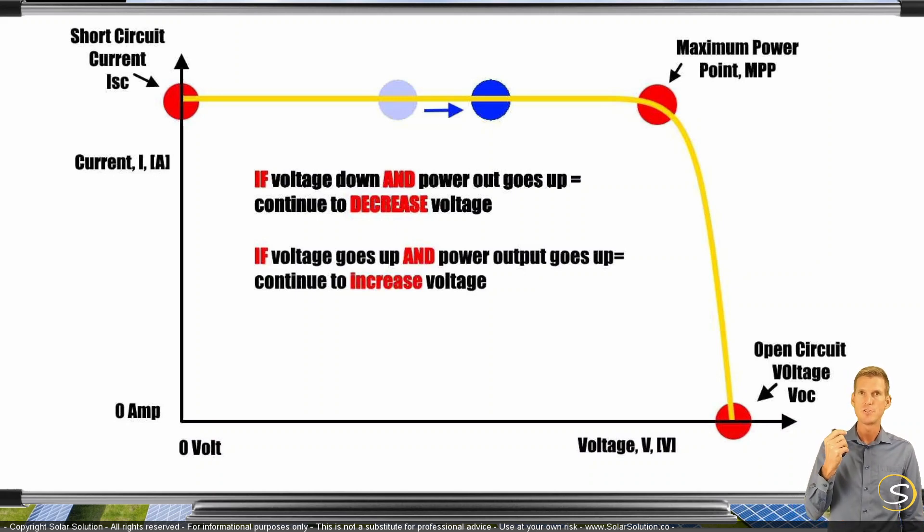Because it tries to achieve the maximum power output, which is the result of voltage times the amperage, by continuously adjusting the voltage. And it will try to hover. It's never stationary. It will try to hover around that maximum power point. And since it's hovering around that point, it's also really flexible.